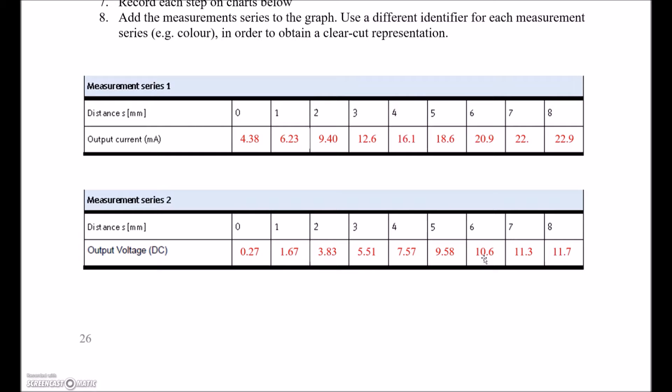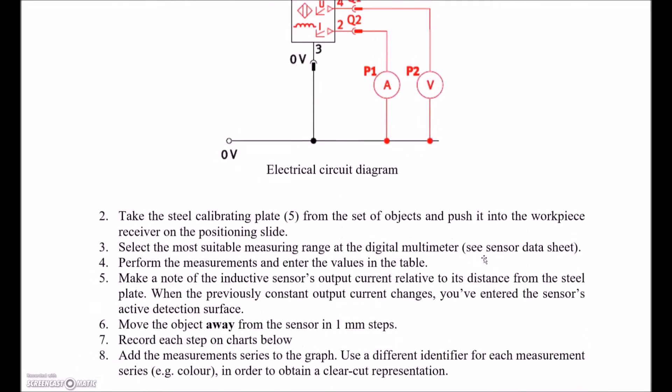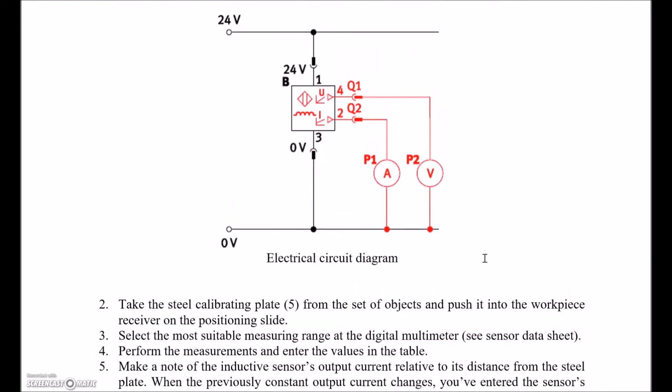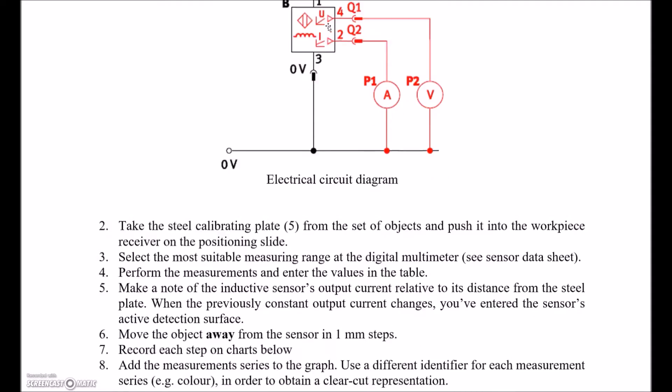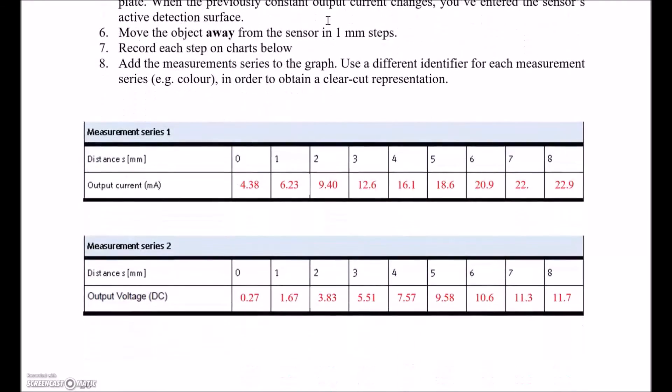If we take a look at the other connections, so you're going to turn this sensor off and reconnect it with the ammeter. You're looking at DC current, so put it in the milliamp port of the meter and make sure that you have it set for DC current. And then looking there again, we have 6 mils of nominal travel. So we should see 4 to 20 milliamps corresponding to our 0 to 6 mils of travel.